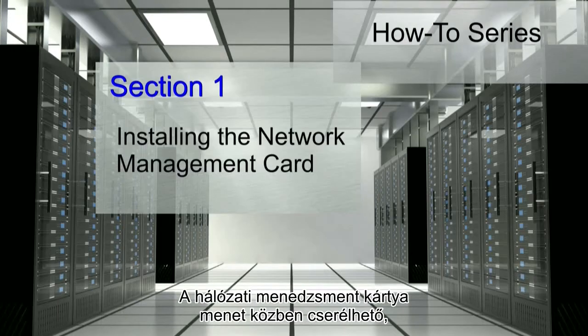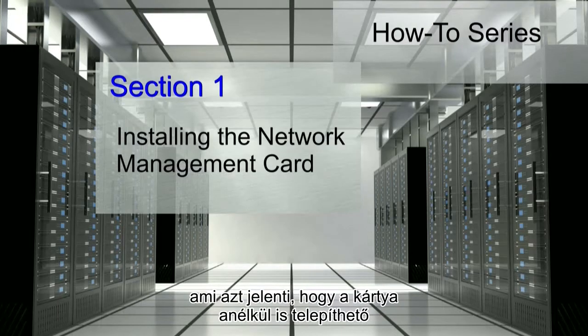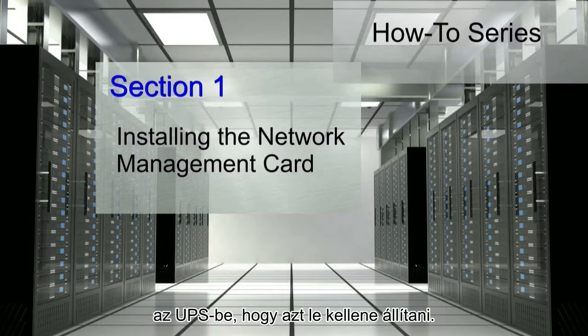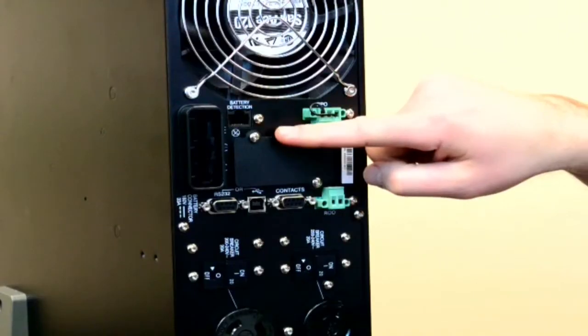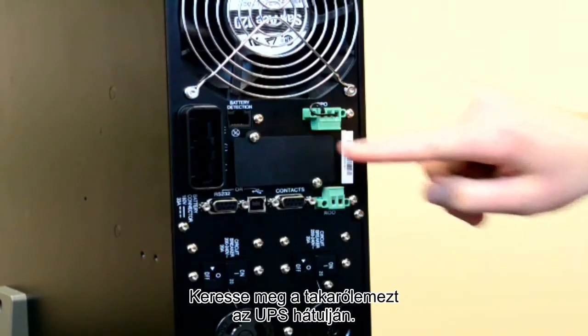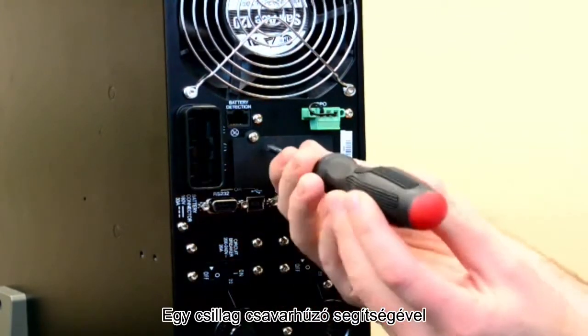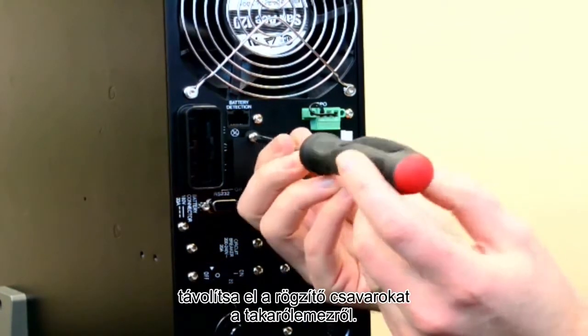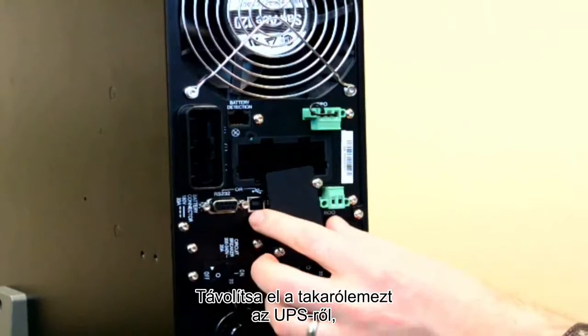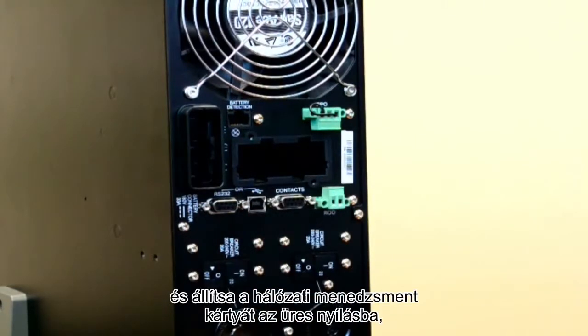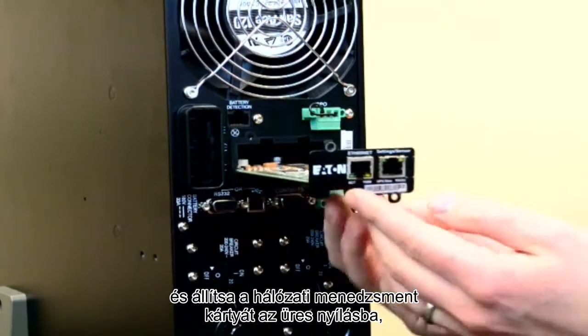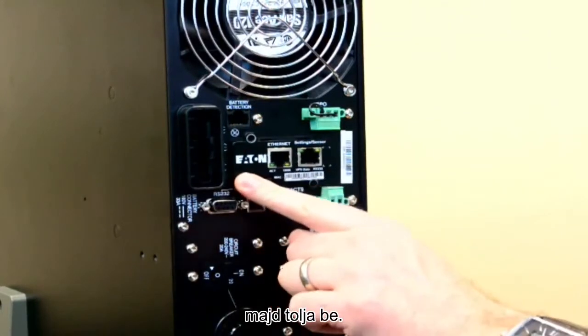The network management card is hot swappable, which means that the card can be installed into the UPS without shutting it down. Locate the blanking cover on the back of the UPS. Using a Phillips screwdriver, remove the retaining screws from the blanking cover. Remove the blanking cover from the UPS.